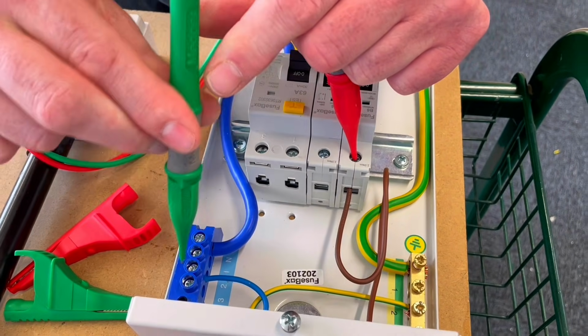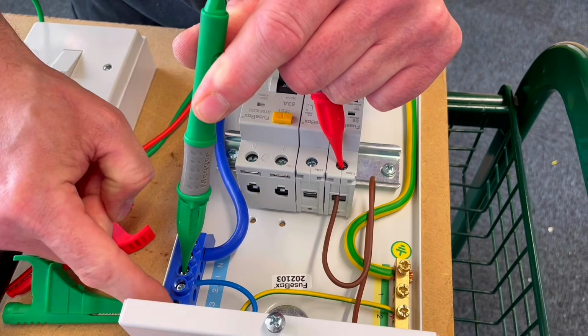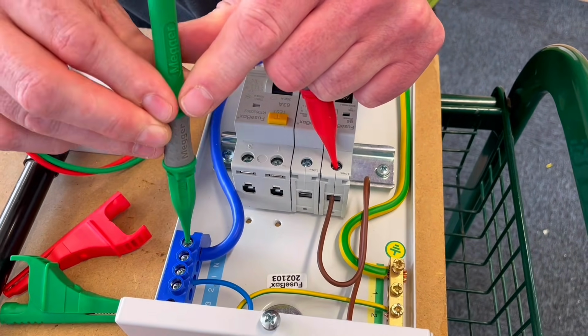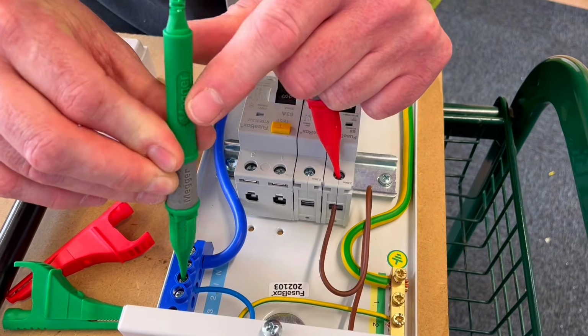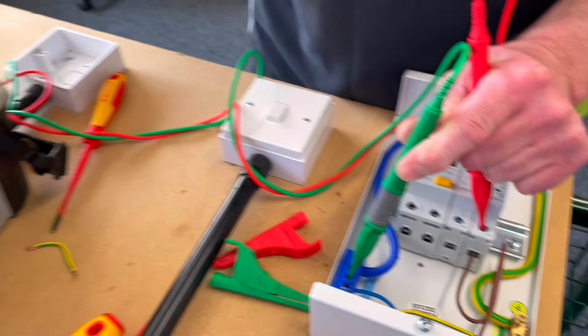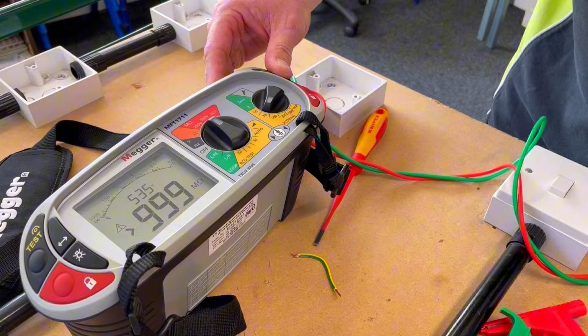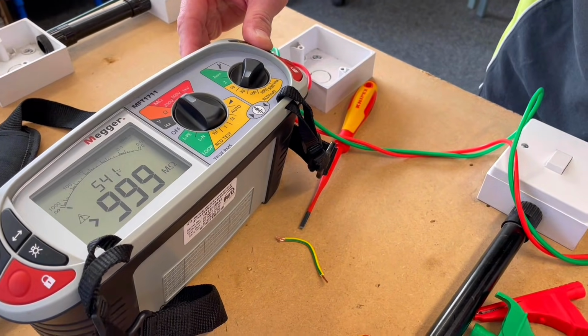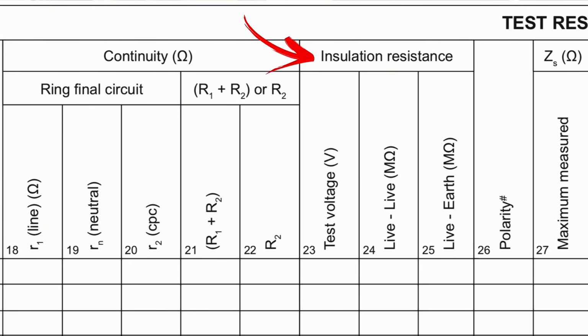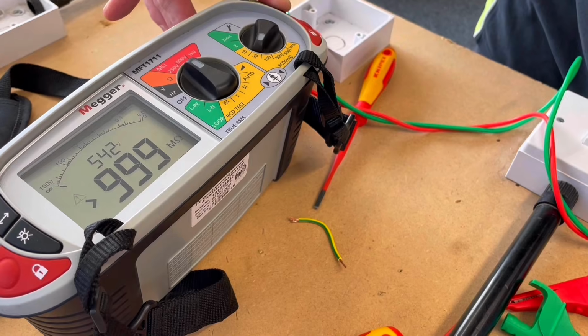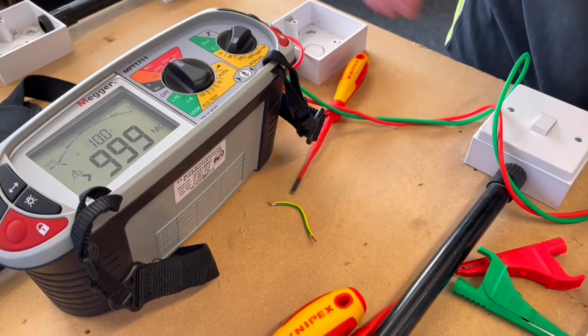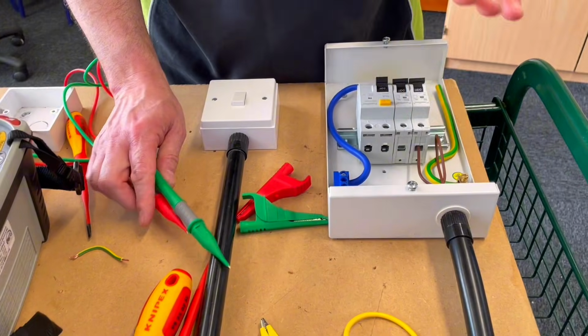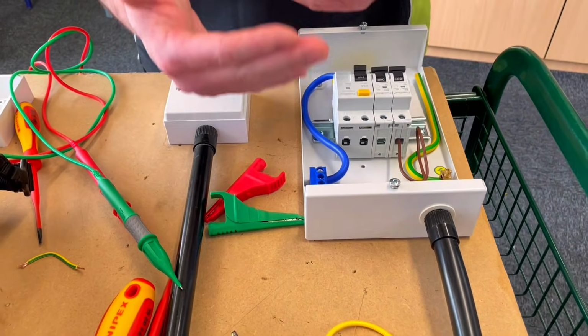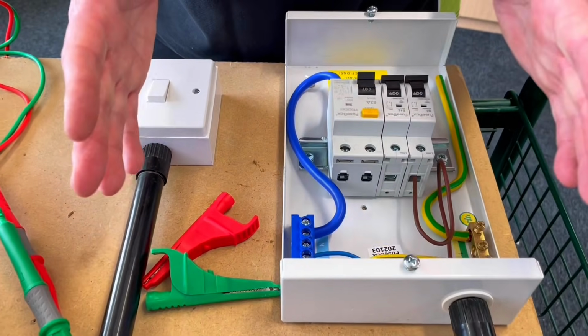Again, it wouldn't matter where I go. So I know that's the terminal I'm testing, and people get obsessed with putting it on top of there. This is a solid bar, so it wouldn't matter where I probed onto. So I'm in those positions there. I'm going to press and hold. And again, I've got a reading greater than 999 megohms, often called megaohms. Okay, so greater than the scale of the machine can read. So a lot greater than the minimum accepted in BS 7671's On-Site Guide of 1 megohm. Certainly greater than the 20 megaohms suggested in Guidance Note 3.